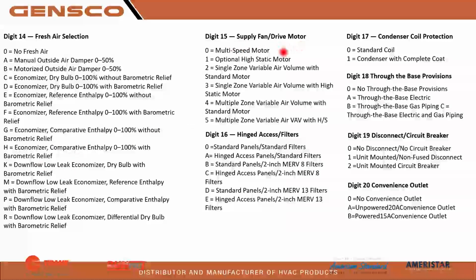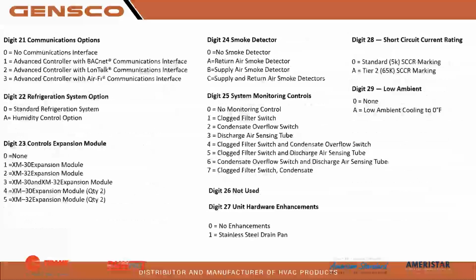Your supply fan multi-speed motor is 0. Most of them are going to have the multi-speed motor. Digit 16, your accessories, if it's got the convenience outlet ordered and whatnot. Your communications, this is another one I pay attention to. You have to order it if you're using it for BACnet or some kind of building automation system, BAS.